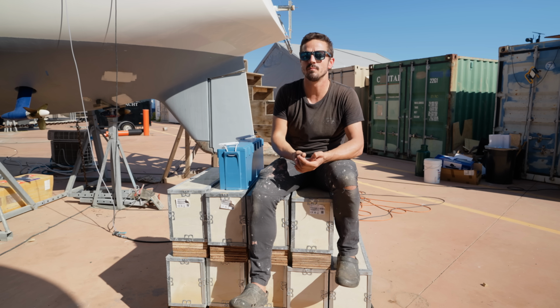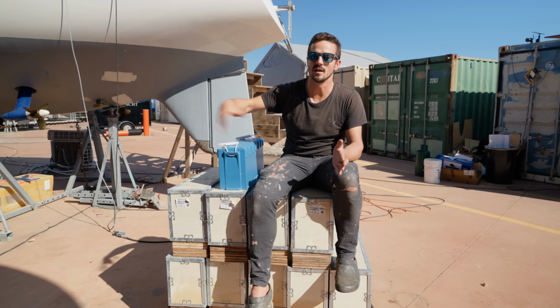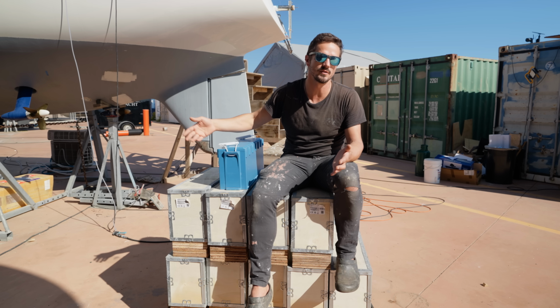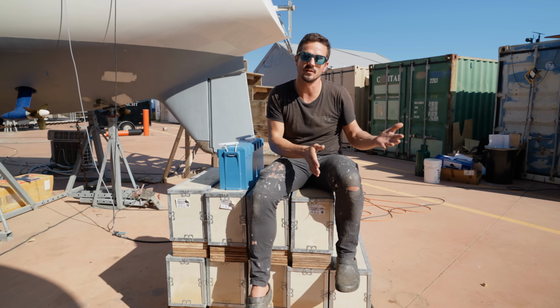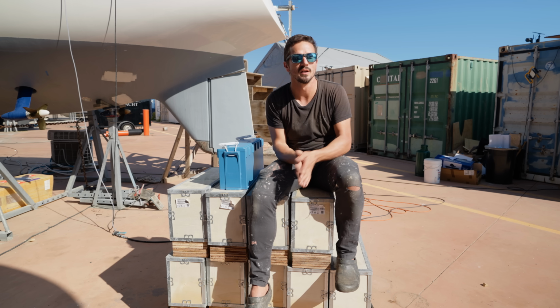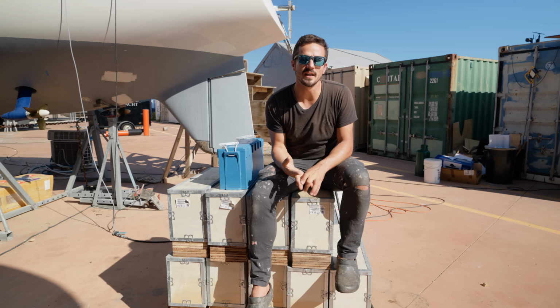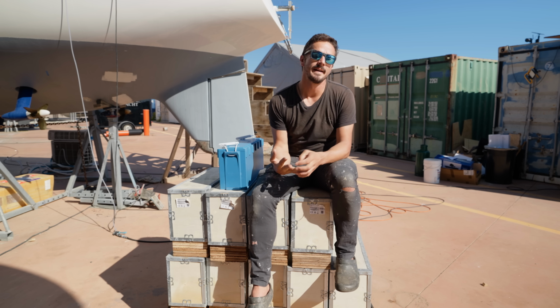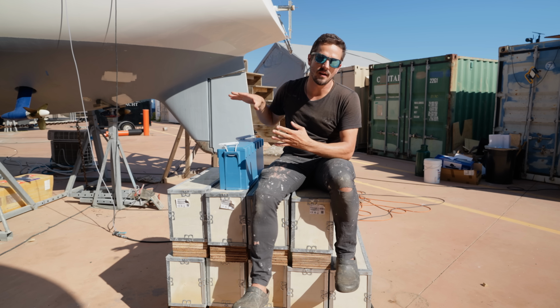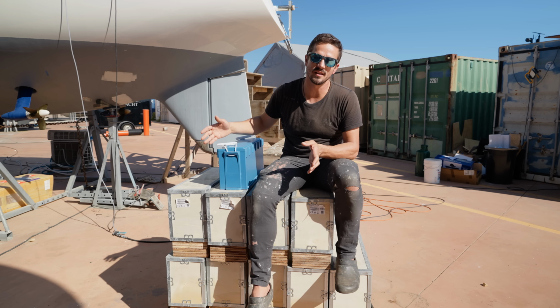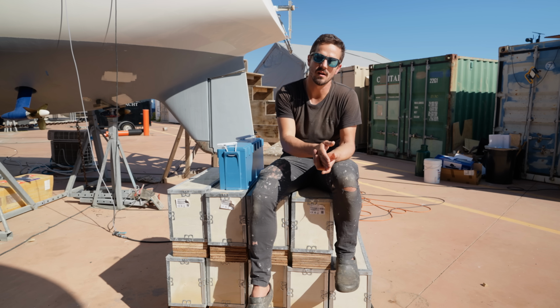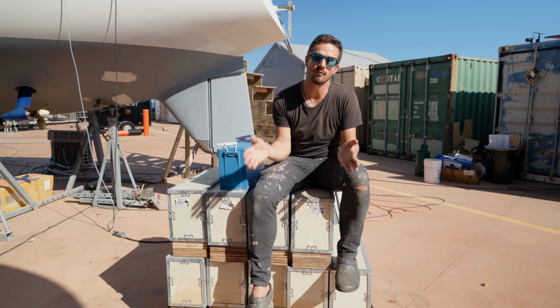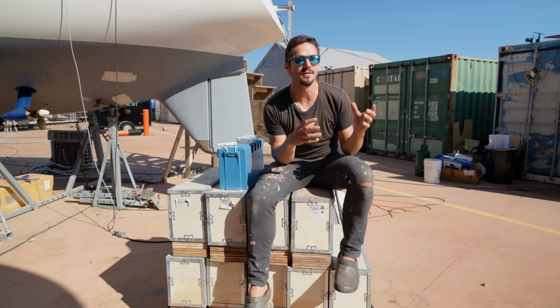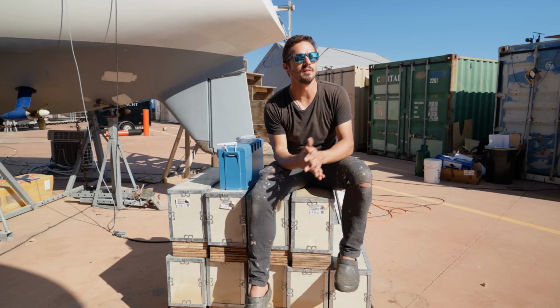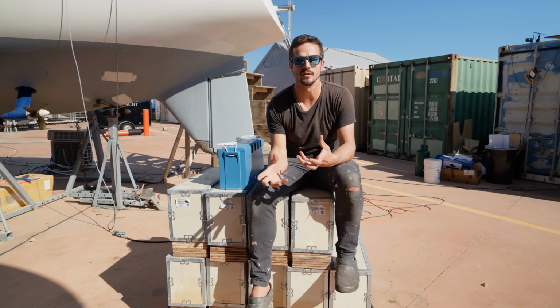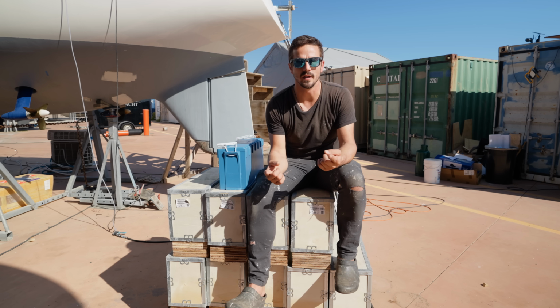They're very rare, but if you have a bank of 5 of these batteries and 1 or 2 of them for some reason get damaged, or the fuse blows, the others can still run all our systems. It's our second level of redundancy. However, having these battery banks the size they are, 5 batteries in parallel, all at 48 volts, we've run into a design issue, and we'll need a creative solution to solve it.